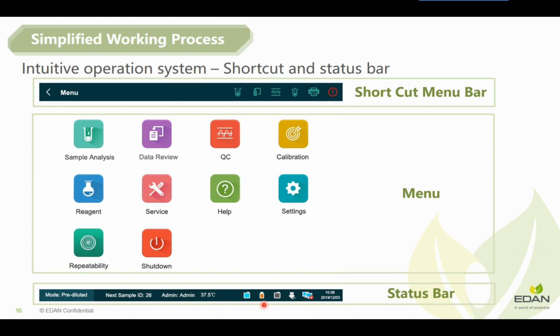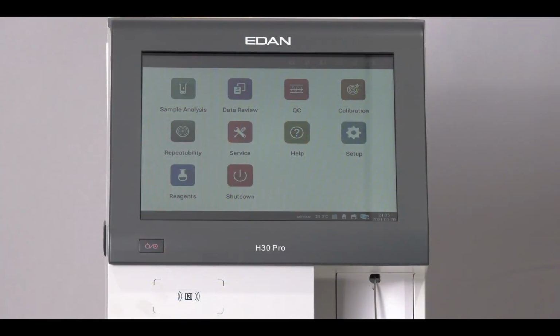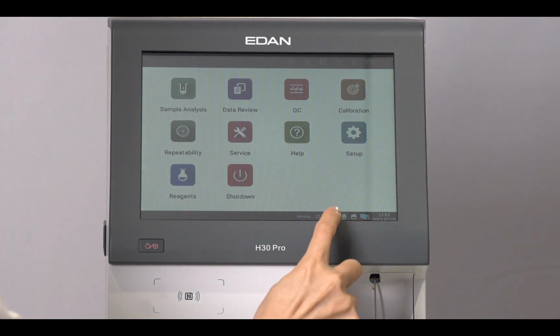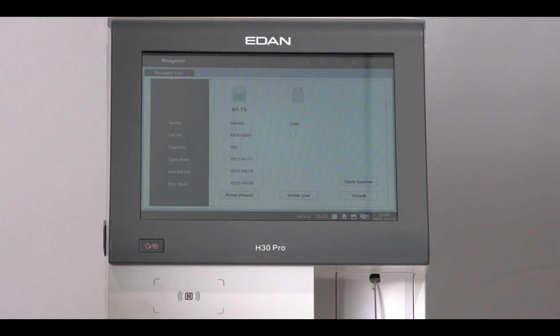For example, when the analyzer is running out of reagent, you may either click on the reagent icon to manage the reagent, or remove the alarm here with simply one click. The system is developed based on the Android system, so you will have a similar operation experience as using your smartphone. Okay, let me show you the operation on the instrument. When the analyzer is empty, the icon will blink and the alarm turns red. Click either of the icons. You can then manage the reagent.